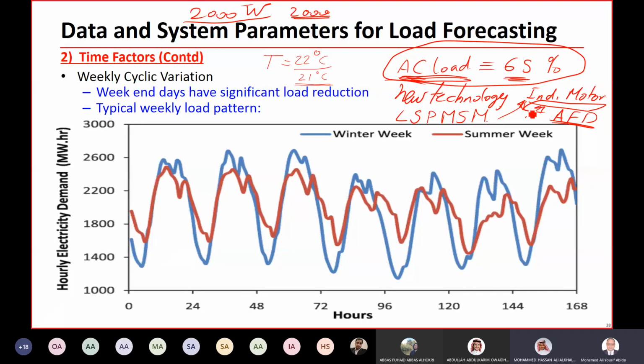Yes, the starting of the AC, of course, consumes more. You have covered the induction motor in 360, right? The starting current will be 6 times the full load current in an induction motor. This current will last about 1 second, or a few milliseconds, and then go to the steady state value, the full load current.